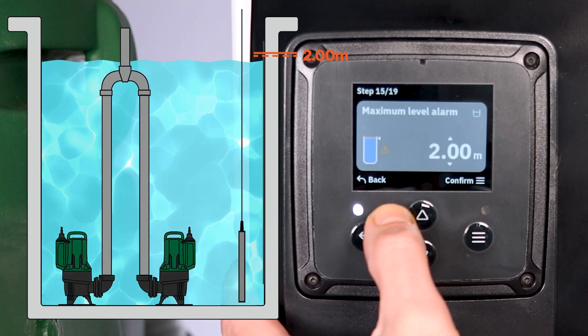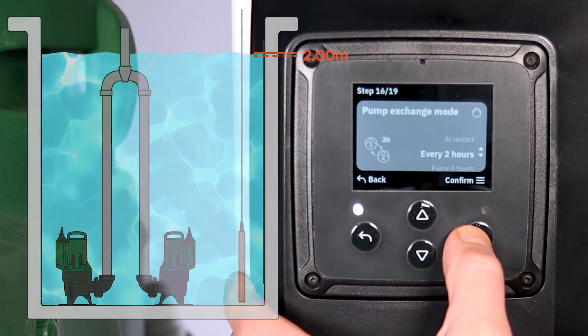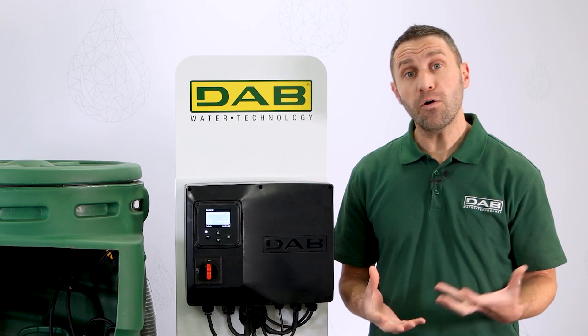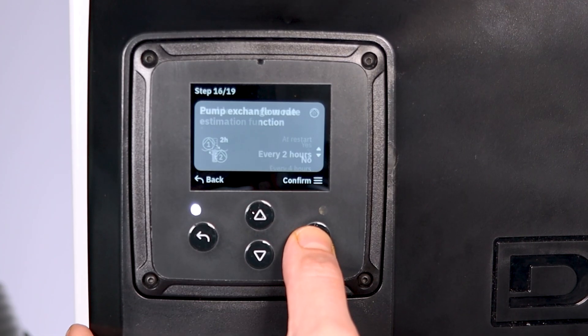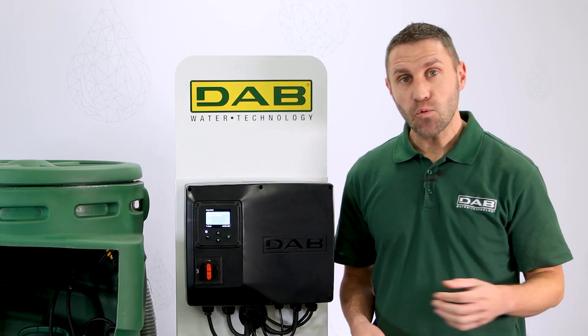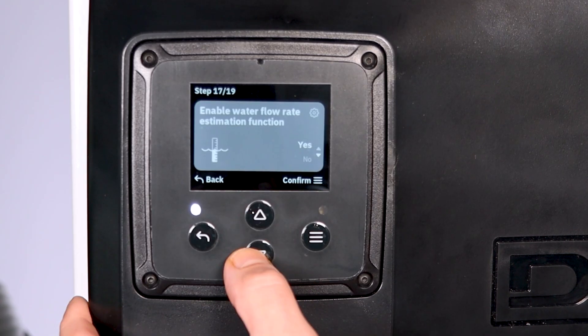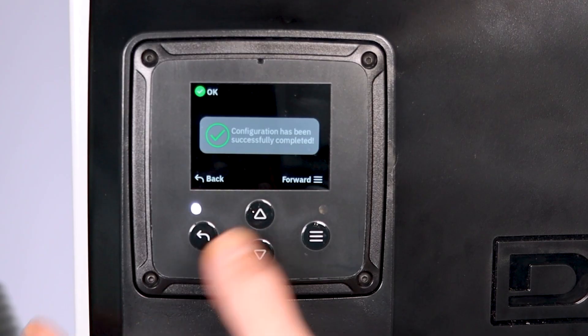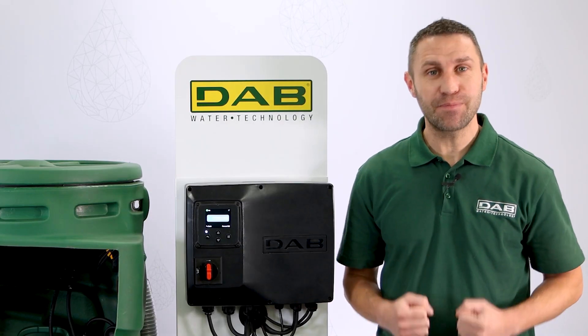The last level we choose is the maximum level for the threshold alarm, which I will set at about 90% of the full capacity of the pit. We select how often the pumps exchange priority and finally we can choose to enable the flow rate estimation or not. And the configuration is completed.